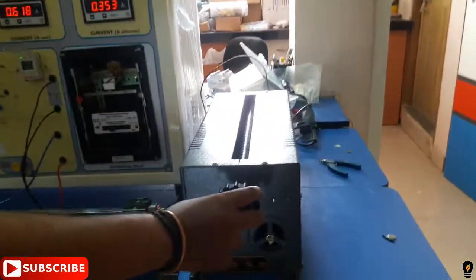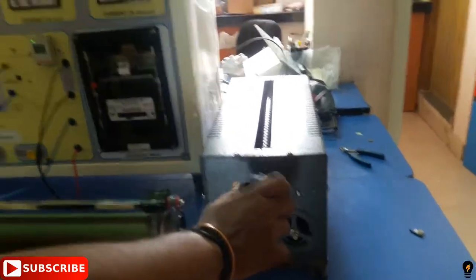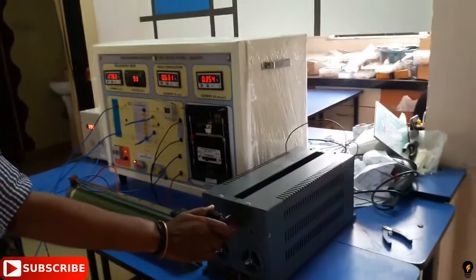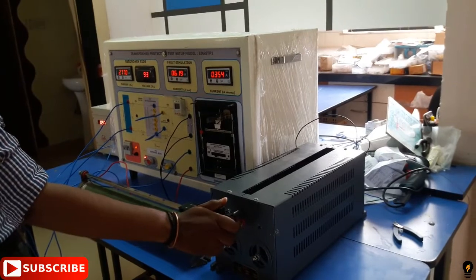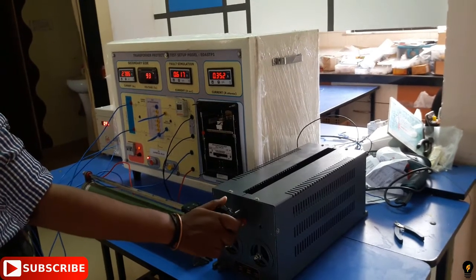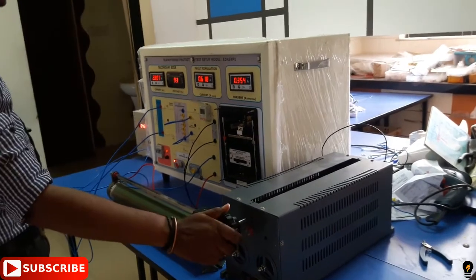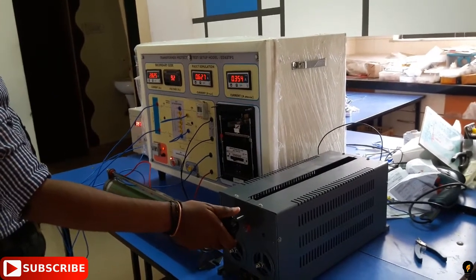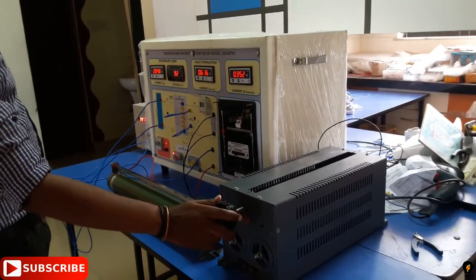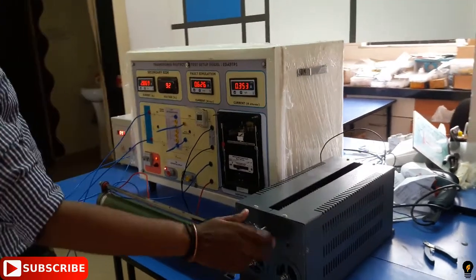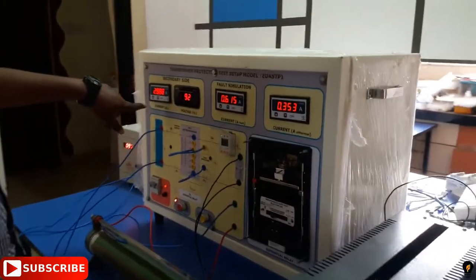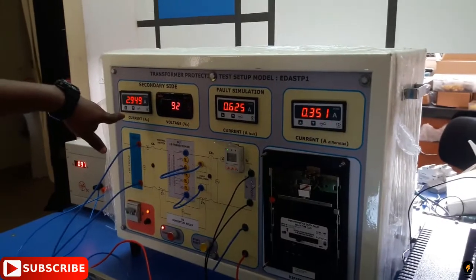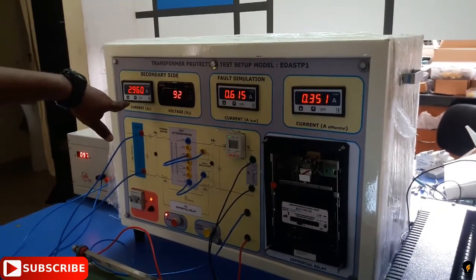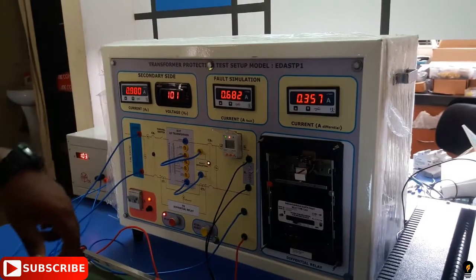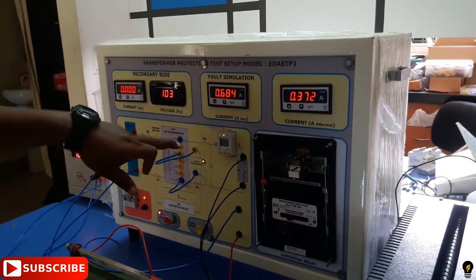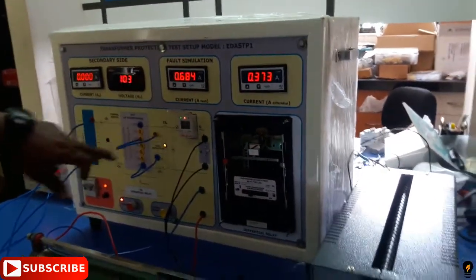This is a single phase transformer with several tappings from 0 to 50% on the secondary side. This provides a way to carry out interturn fault. In this system, we have used two protection relays, differential relay and overcurrent relay. Relays are used to protect the transformer from interturn fault and overcurrent respectively. This is the short description about the transformer protection test setup. Let's go for the working of the transformer protection test setup.